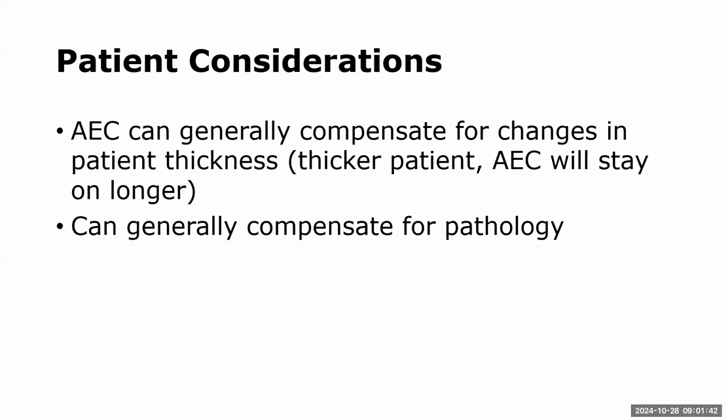With AEC, it's just not going to stay on as long, right? It's going to reach that preset charge quicker. It's going to send a timer signal quicker to cut off. So it takes care of it for you. That is the beautiful part of AEC, that it compensates for a lot of different things and takes that worry out of our hands, okay?